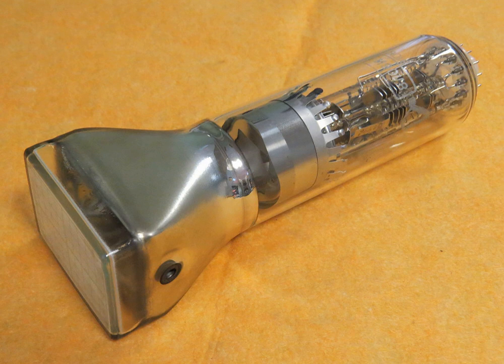Topic: Selection. For work at high frequencies and with fast digital signals, the bandwidth of the vertical amplifiers and sampling rate must be high enough. For general purpose use, a bandwidth of at least 100 MHz is usually satisfactory. A much lower bandwidth is sufficient for audio frequency applications only. A useful sweep range is from 1 second to 100 nanoseconds, with appropriate triggering and, for analog instruments, sweep delay. A well-designed, stable trigger circuit is required for a steady display. The chief benefit of a quality oscilloscope is the quality of the trigger circuit.